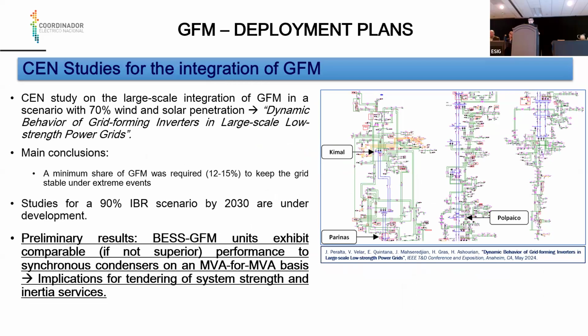Regarding deployment plans, several years ago, we started studies for grid forming integration. We studied a large scale integration of grid forming in a scenario with 70% of solar and wind penetration. Just a note aside, last September, we reached 80% of wind and solar penetration based on inverters. In the figure, you can see the modeling of our system in the software, where we have more than 600 or 700 buses, more than 200 power plants, and thousands of control blocks in that system. So the simulation takes very long.